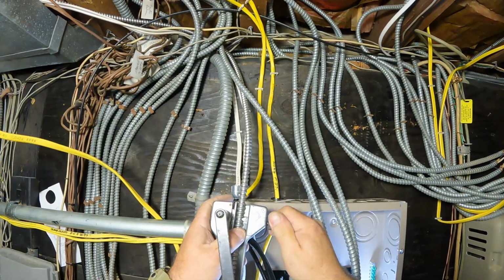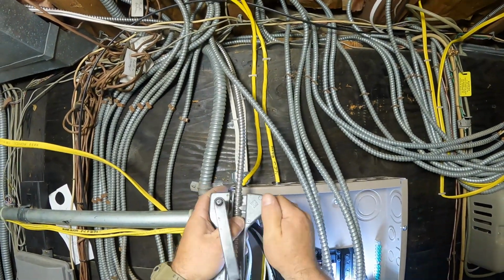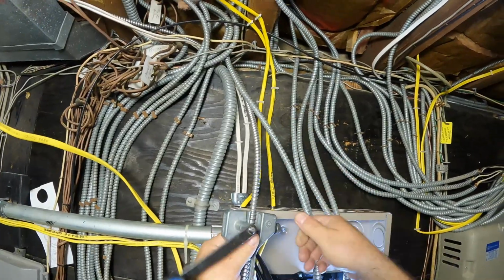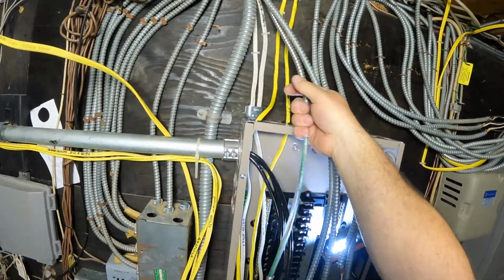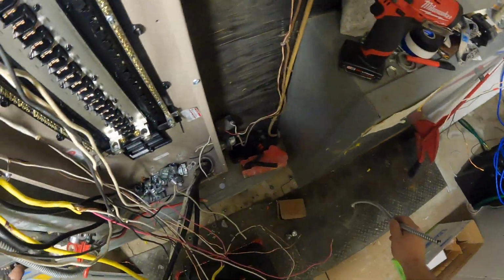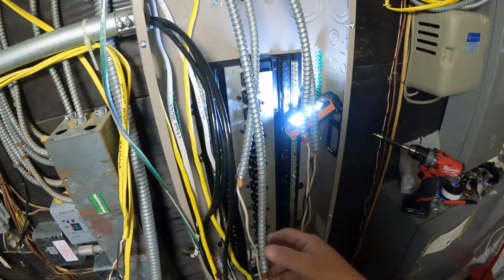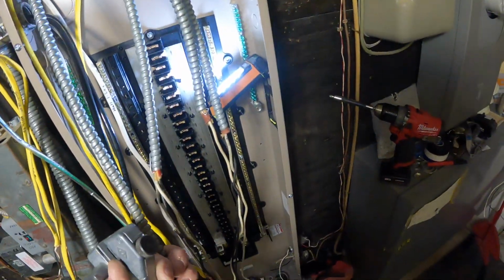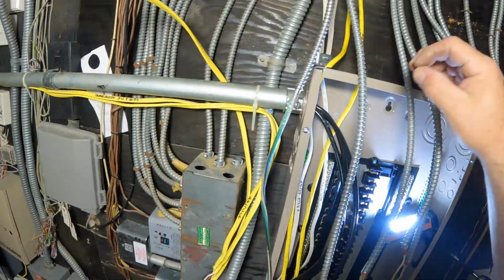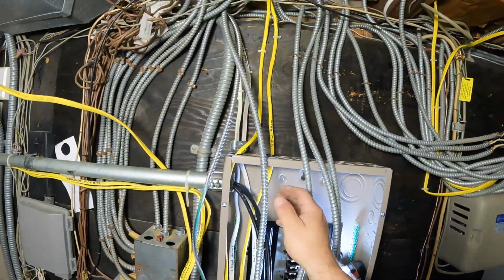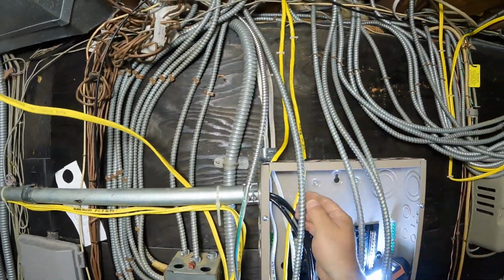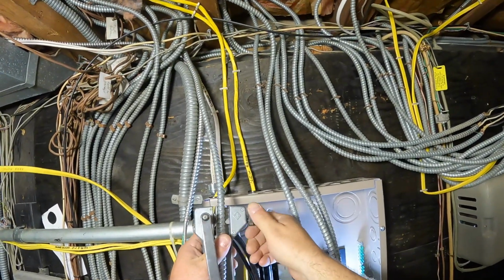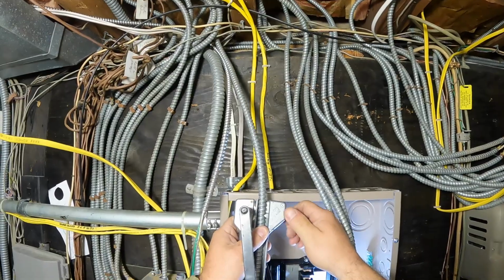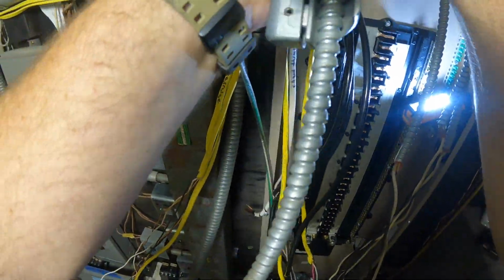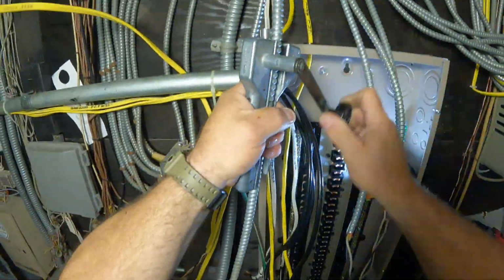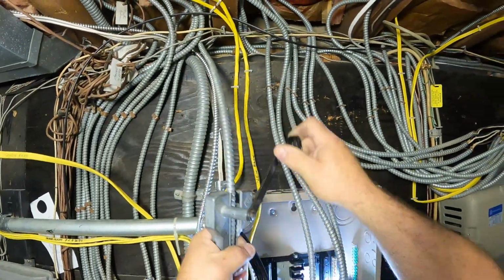Here I'm using Greenlee BX cutters. That's a term that pretty much everybody knows, BX, and I still call it BX, but the real term is armored cable. And actually, that's MC cable, not even BX cable or armored cable. I hope you're not confused. MC cable is a cable that actually has an insulated equipment grounding conductor, that green conductor. That's how you know it's MC cable. Armored cable, aka BX cable, will not have that insulated ground, and the outer sheathing acts as the equipment grounding conductor. But anyway, I'm using my Greenlee connectors, my strippers here.